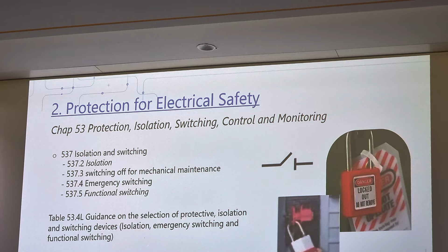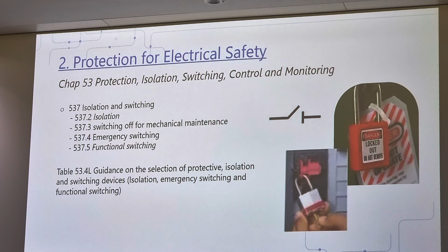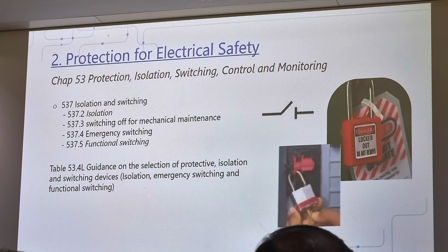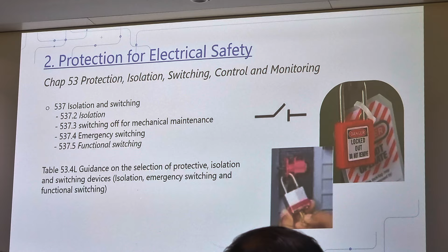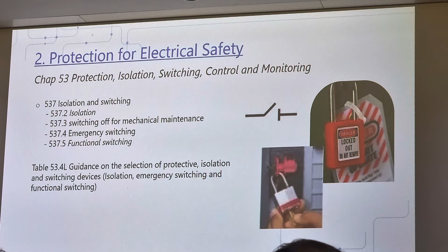Now, there's a table in section circuit breaker, you have socket outlet, you have MCB, controller, all kinds of devices. So, which can provide what function? The source of information is this table 53.4. It tells you what this device can do, whether it can work as isolation, whether it can work as a switching, whether it can work as an emergency switching. Right? Because one device can have multiple functions. Same device can serve as an isolation, can serve as a switching. But some device can only have one or two of the functions, not all the functions. So you want to understand what are different devices, what they perform, so you can put in the appropriate device at the appropriate location in your electrical installations.